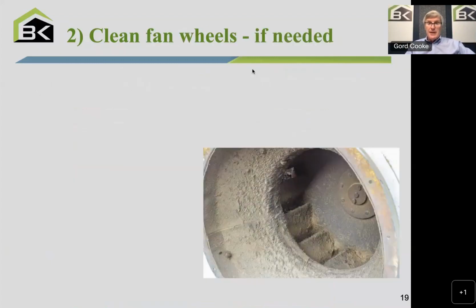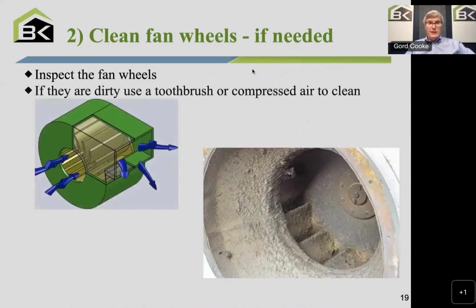And then I'm showing here that we'd like you to inspect the fan wheels. Remember, there were 2 fans. On the left-hand side, you're seeing what we call a centrifugal fan, or sometimes they call it a squirrel cage fan. And you'll notice the one on the right has gotten kind of caked up over time. This is not common. It's not always the case, but it can happen with a unit that hasn't been maintained in 10 or 15 years, or maybe the filters weren't properly done. So you would just take a toothbrush to that. Typically, this can be done with the fan still installed.